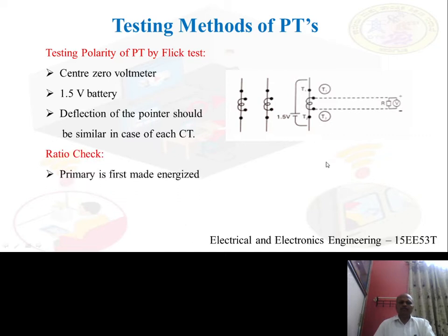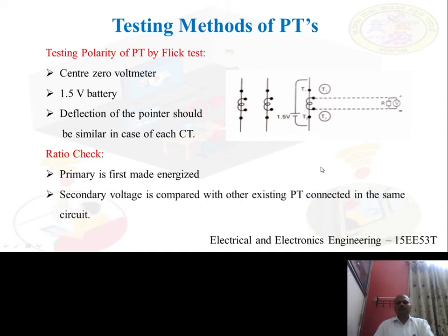In this method, supply is connected to primary and secondary voltage is measured. This value is compared with the connected PTs in the same circuit. Third one, phase sequence check. By using phase sequence meters, phase sequence of 3 terminals is checked.